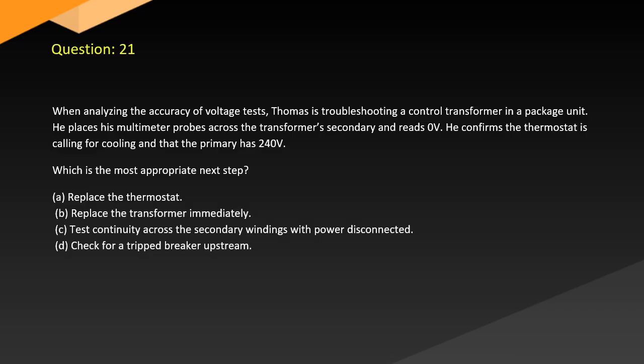Question 21. When analyzing the accuracy of voltage tests, Thomas is troubleshooting a control transformer in a package unit. He places his multimeter probes across the transformer's secondary and reads 0. He confirms the thermostat is calling for cooling and that the primary has 240 V. Which is the most appropriate next step? A. Replace the thermostat. B. Replace the transformer immediately. C. Test continuity across the secondary windings with power disconnected. D. Check for a tripped breaker upstream.